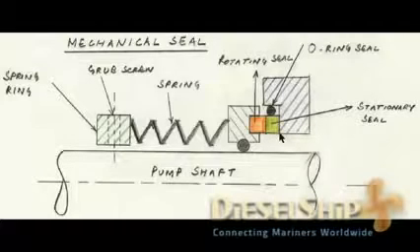So you have three important seals here, as we discussed earlier. One is the primary seal, which has the sealing surface over here, that is between the ceramic layer and the carbon layer. You have a seal which is primary, and you have two secondary seals. That is one secondary seal which is the O-ring for the stationary part, and one O-ring for the rotating part.